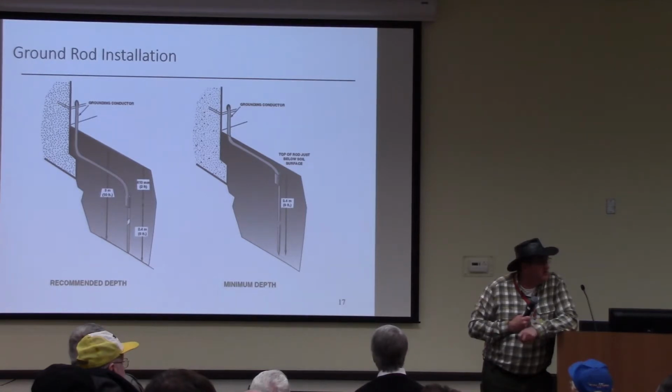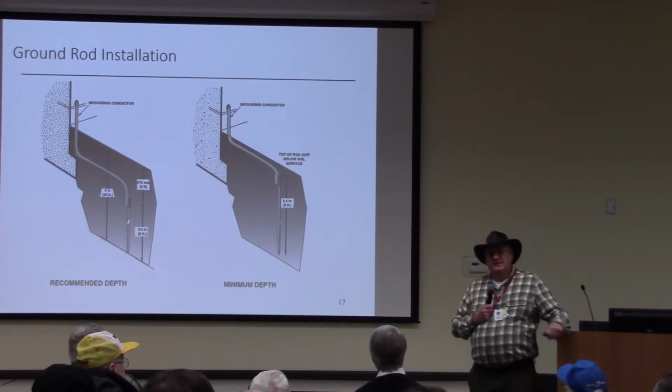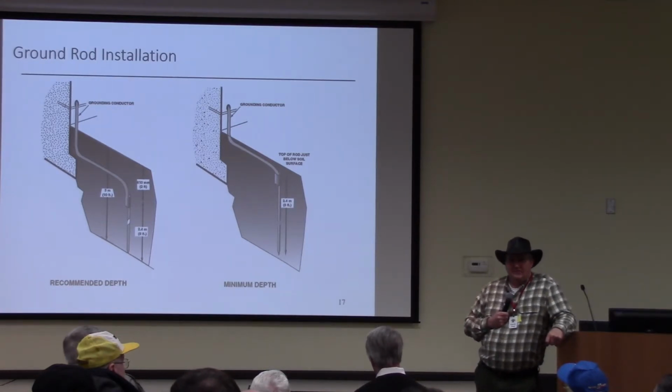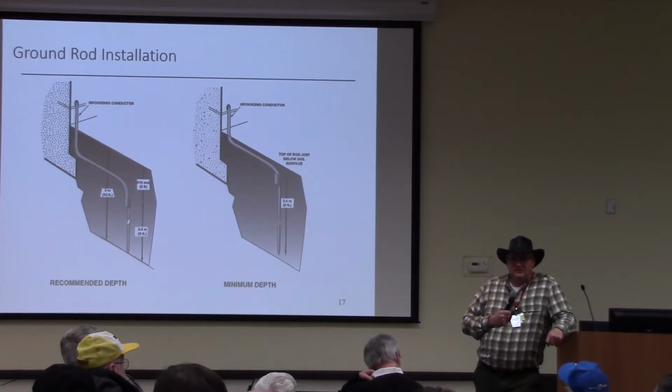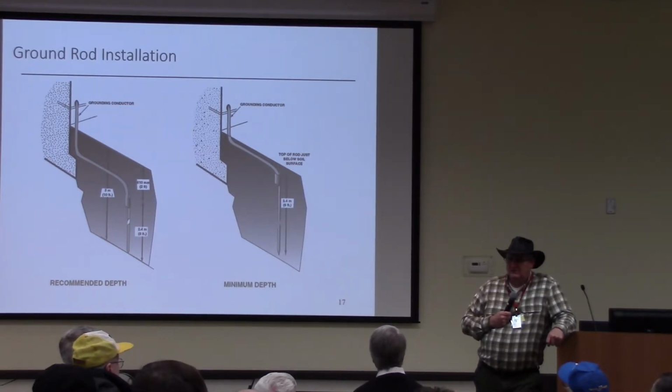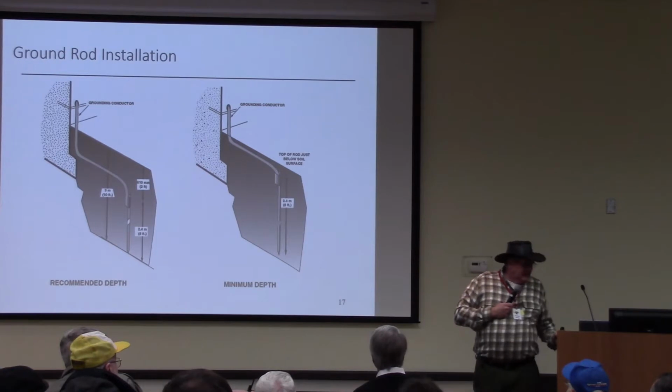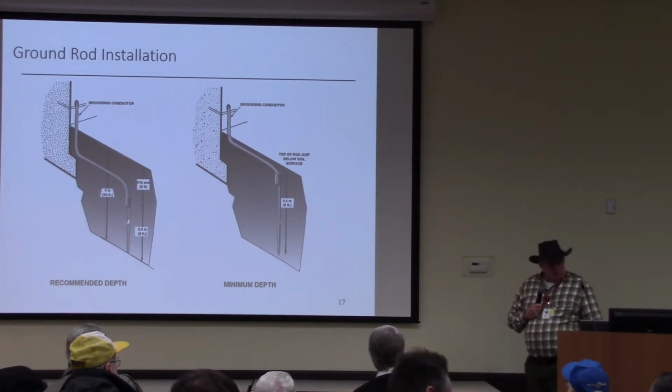You're going to hate this guy too, but I had a cable guy come and he was testing the line and things like that. And he felt it necessary to disconnect the ground for his machine to work, for his device to get a good signal, and then he hand tightened it back. That's not a good application, no. That can cause more problems.